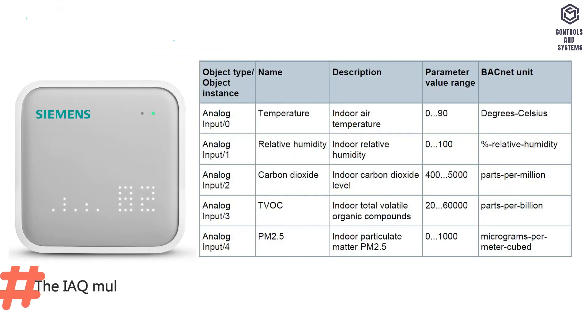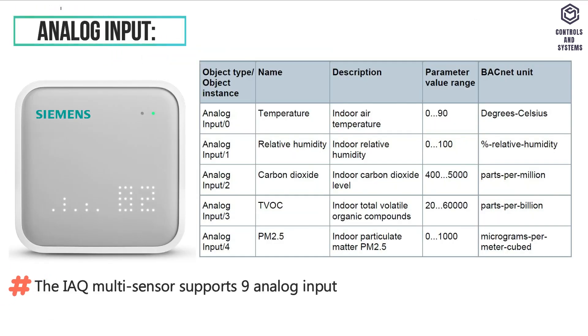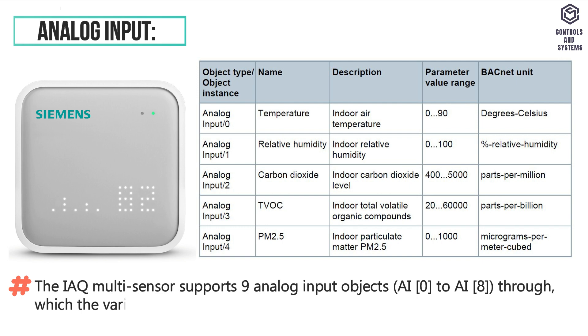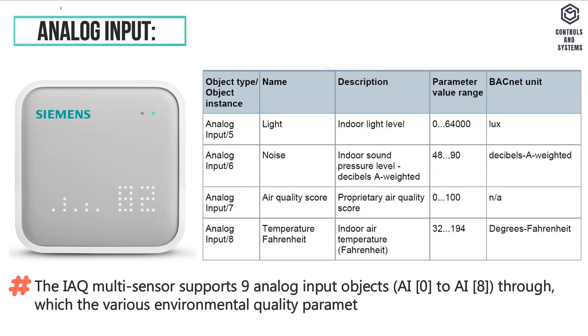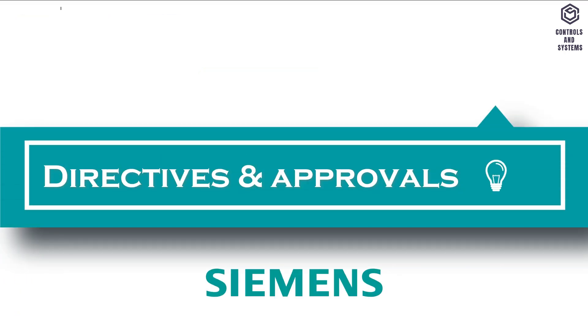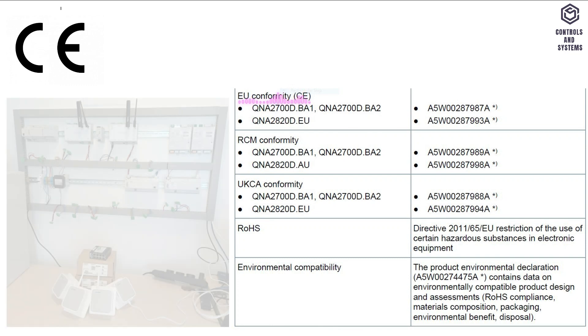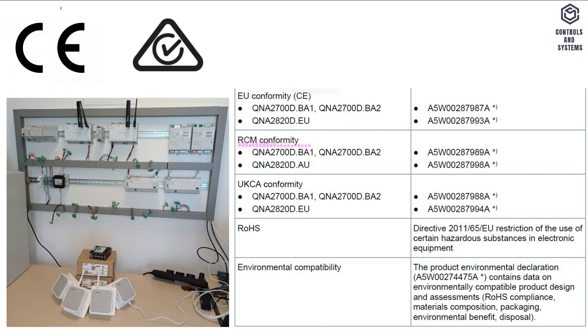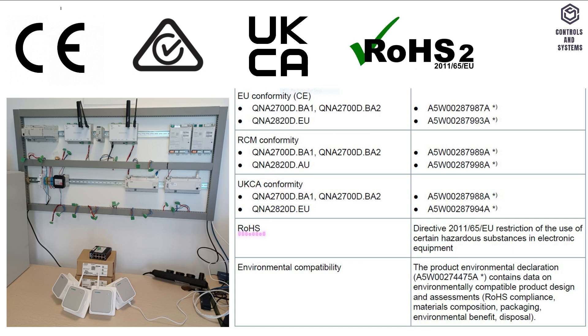The IAQ Multisensor supports 9 analog input objects, AI0 to AI8, through which the various environmental quality parameter measurements can be read out by a BACnet client. Directives and approvals include: European Conformity (CE), Regulatory Compliance Mark (RCM), UK Conformity Assessed (UKCA), and Restriction of Hazardous Substances (RoHS).